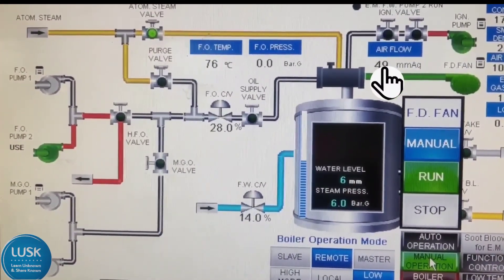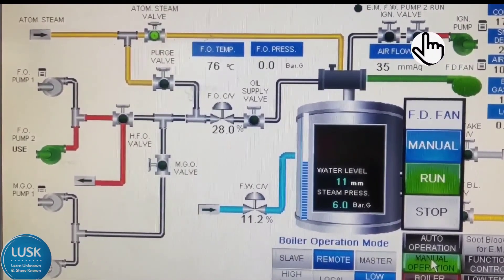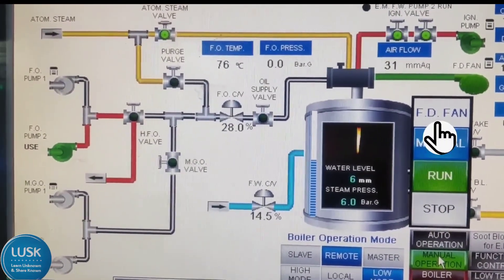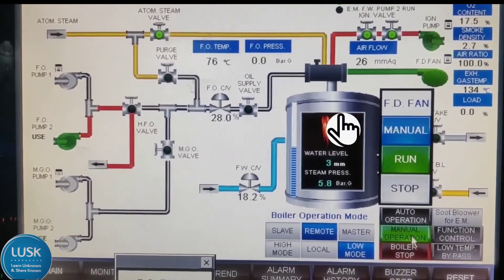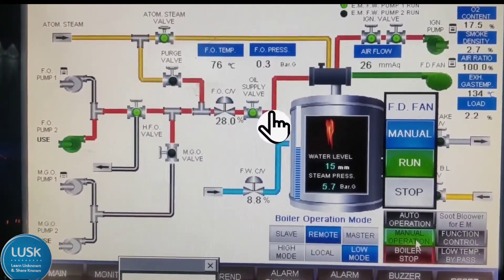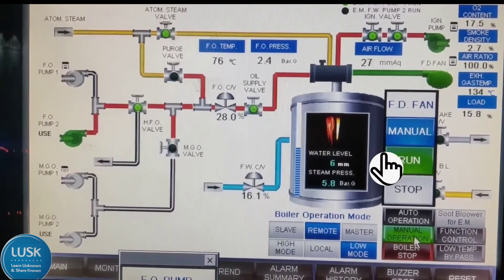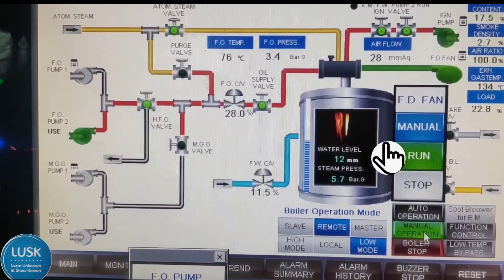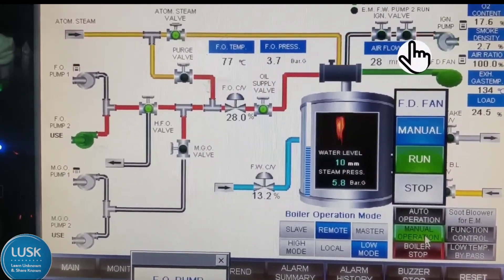After the ignition pump starts, when the flap reaches the minimum value — around 22 — these two valves will open automatically to fire the pilot burner. Now you can see those valves opened and pilot burner is firing right now. Then the oil valve opened and now the main burner has also started firing. There is a flame sensor which detects whether the flame is steady or not. After the flame is steady, the pilot burner stops automatically, and the ignition pump will stop and valves will also get closed.